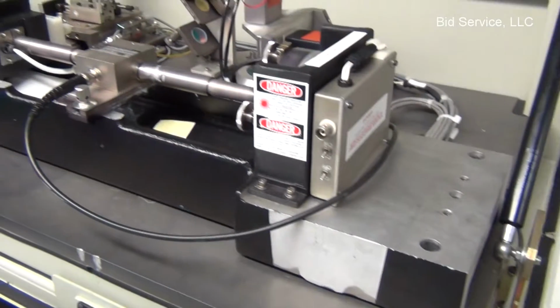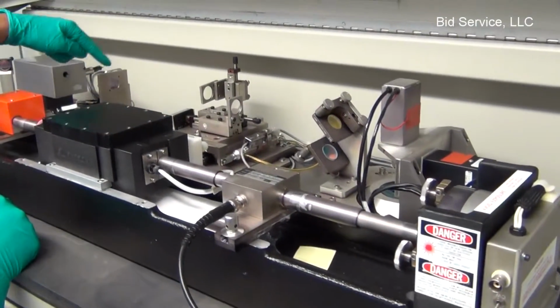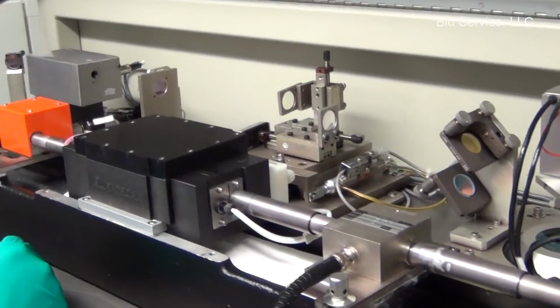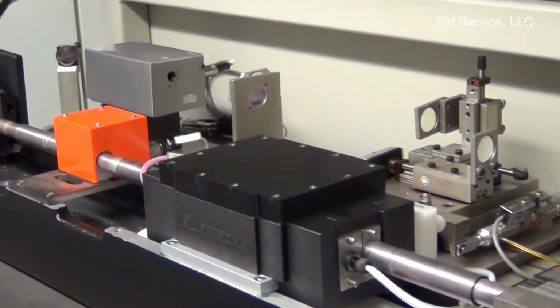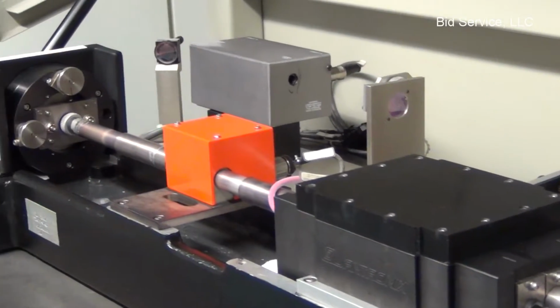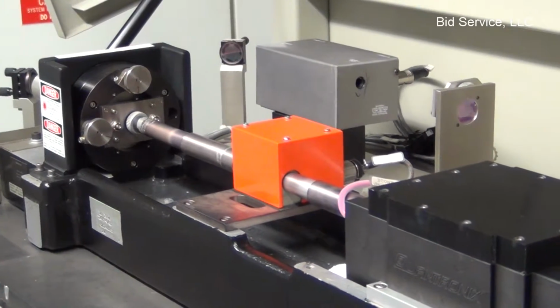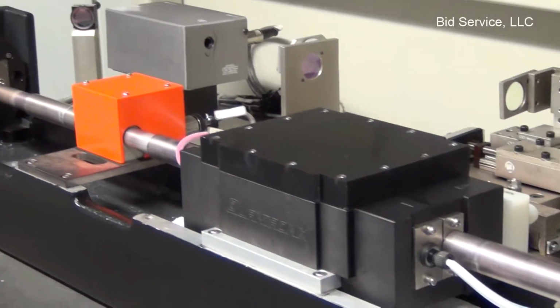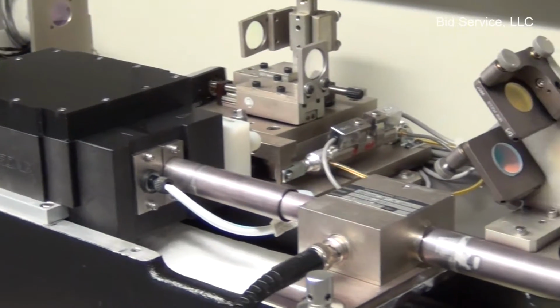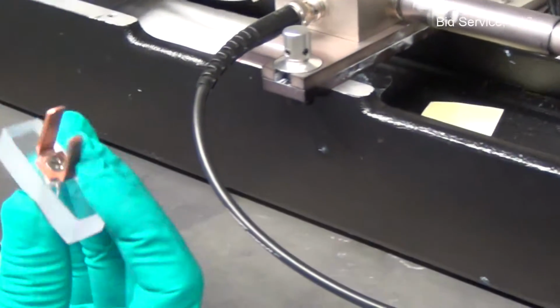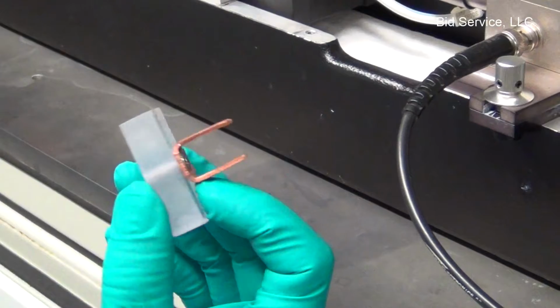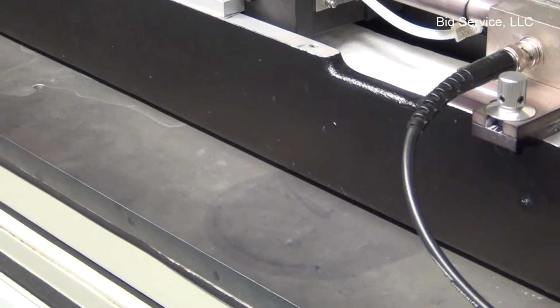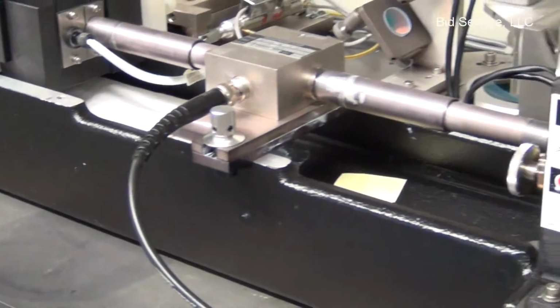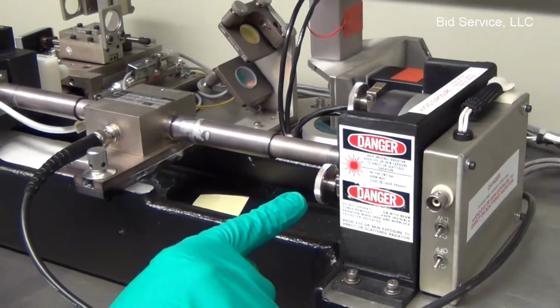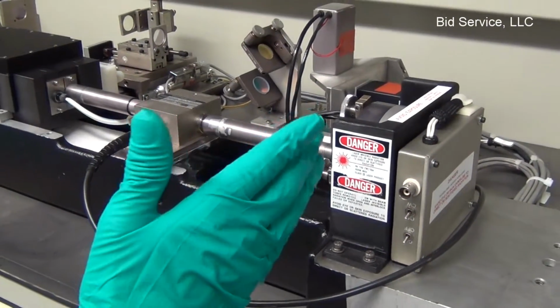Invisible IR laser is in this area, and only at the time of maintenance can these interlock switches be disabled and the laser turned on by using these jumper plugs. No attempt should be made to turn these knobs. These mirrors are aligned and locked using the lock screws.